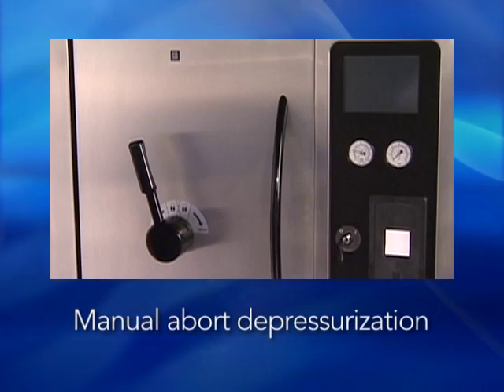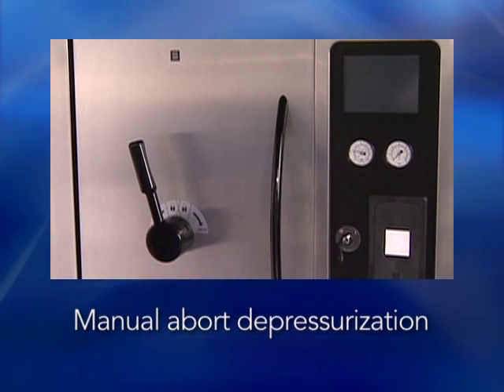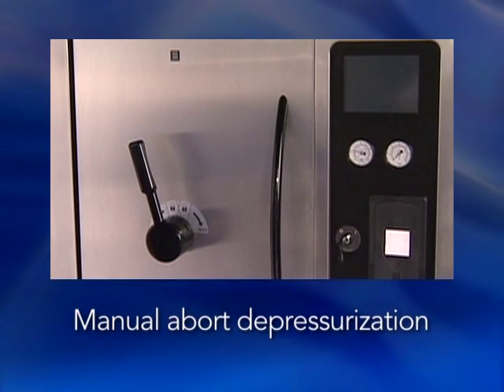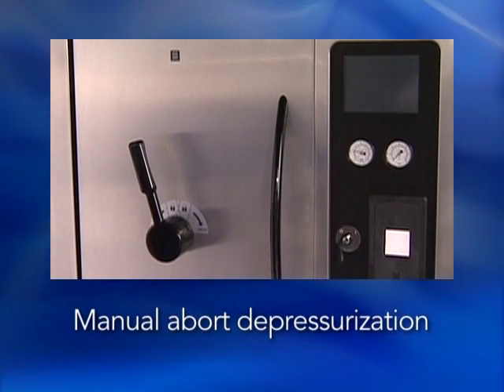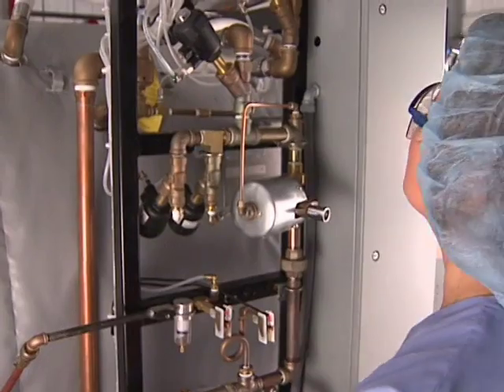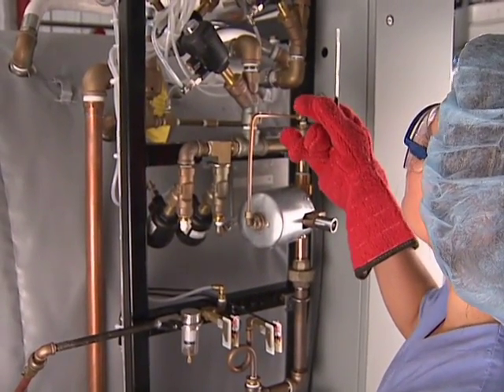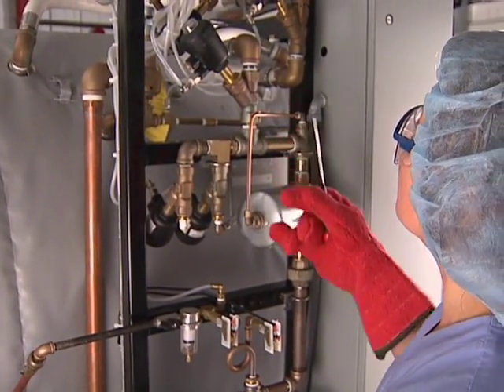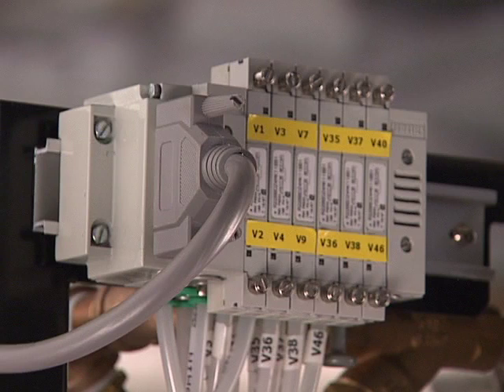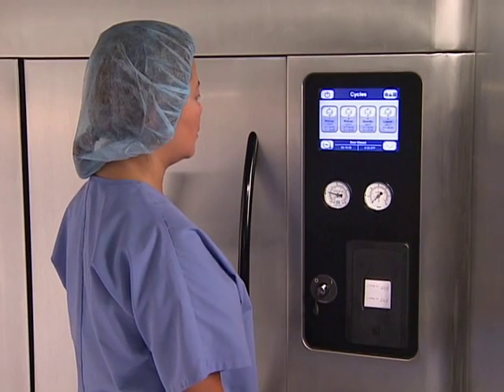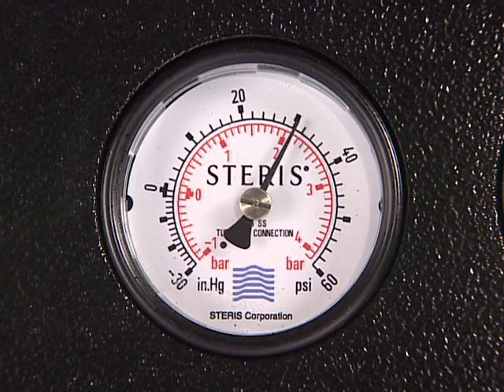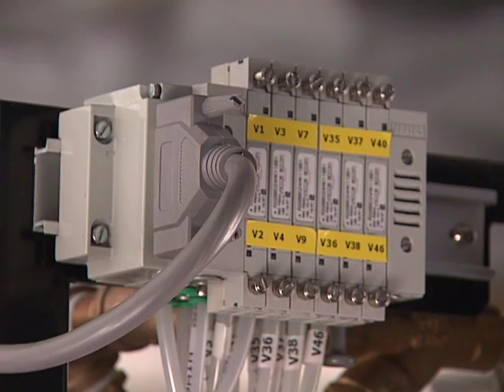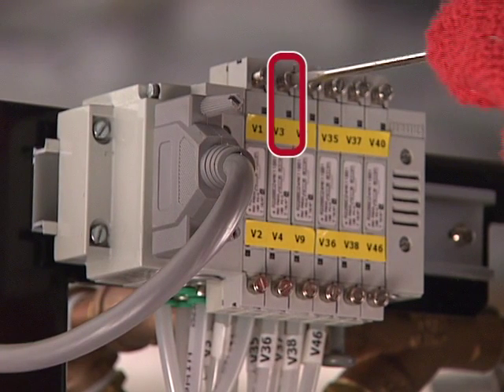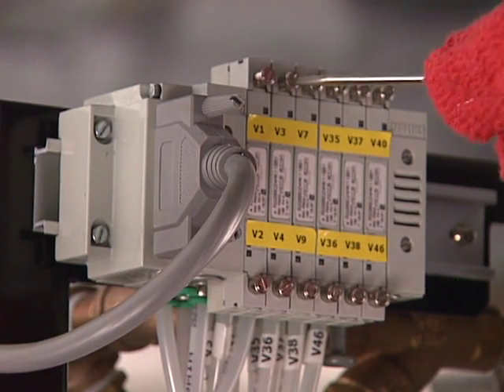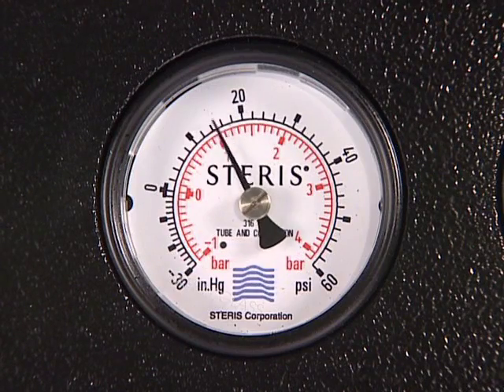If you experience a power outage, you can manually exhaust the chamber and remove the load if necessary. However, you should only perform this procedure if there is an immediate need for those instruments. Before you start, make sure you have a 1/8 inch flat screwdriver handy. You'll also need access to the air manifold in the sterilizer's service area. First, check the chamber and jacket gauges to see if the chamber is pressurized or holding a vacuum. If the chamber is pressurized, use the screwdriver head to push in the V3 valve screw on the air manifold and turn it counterclockwise. This opens the valve and releases the pressure.